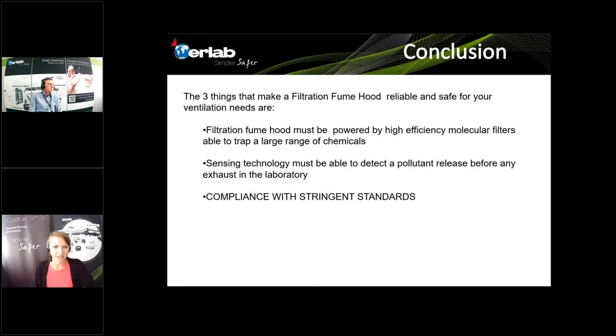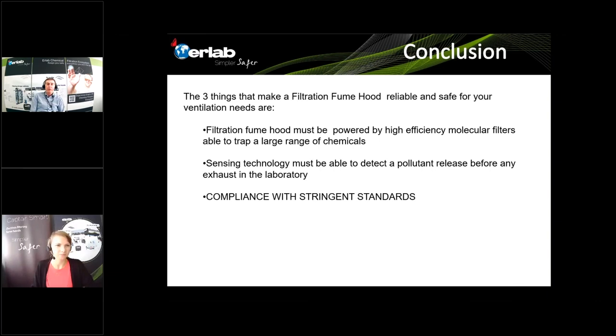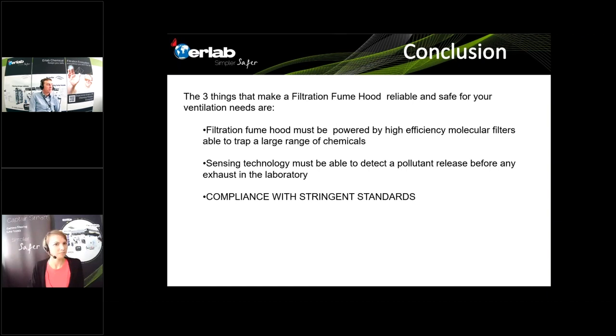Question from Kate: Would using solvents such as heptane prolong the lifetime of the filters compared to pentane, or would this application be better suited to a ducted fume hood? For certain kinds of carbon, yes, heavier solvents improve retention. But it really depends on the activated carbon you use. With the Neutrodine Unisorb filters, the difference between light solvents and heavy solvents is not as large as with classical activated carbon, because we have significantly enlarged the retention capacity for light solvents.